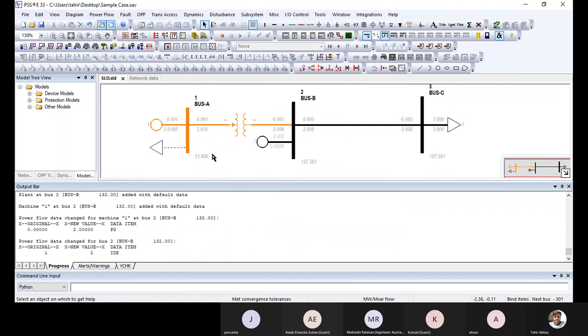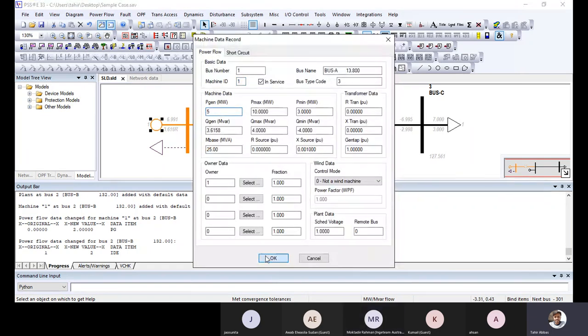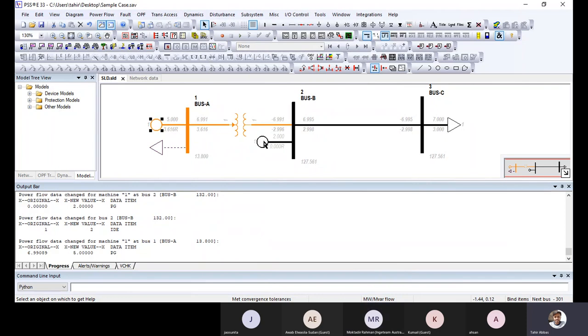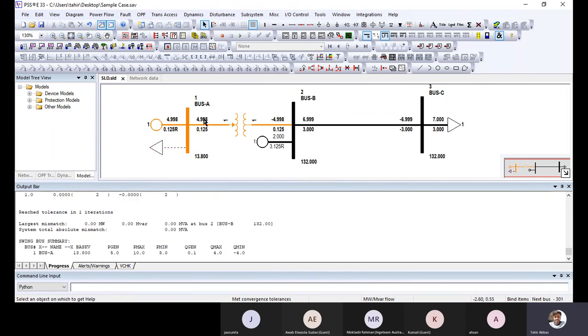Okay. Now see, demand is 7 megawatt, 2 megawatt is here, and 5 megawatt is here. So definitely the 2 megawatt is fed by this generator and the remaining will be from the swing generator. Now I'm solving again. Now you can see of the 7 megawatt demand, 2 megawatt is fed from here and 5 megawatt from here. Yep. The swing is adjusting. Basically, when we solve a larger network, swing is very important. The swing balancing assists us as a system operator, meaning we have a complete idea of our swing. Basically, swing tells the frequency variation, meaning whether demand is balanced or not.